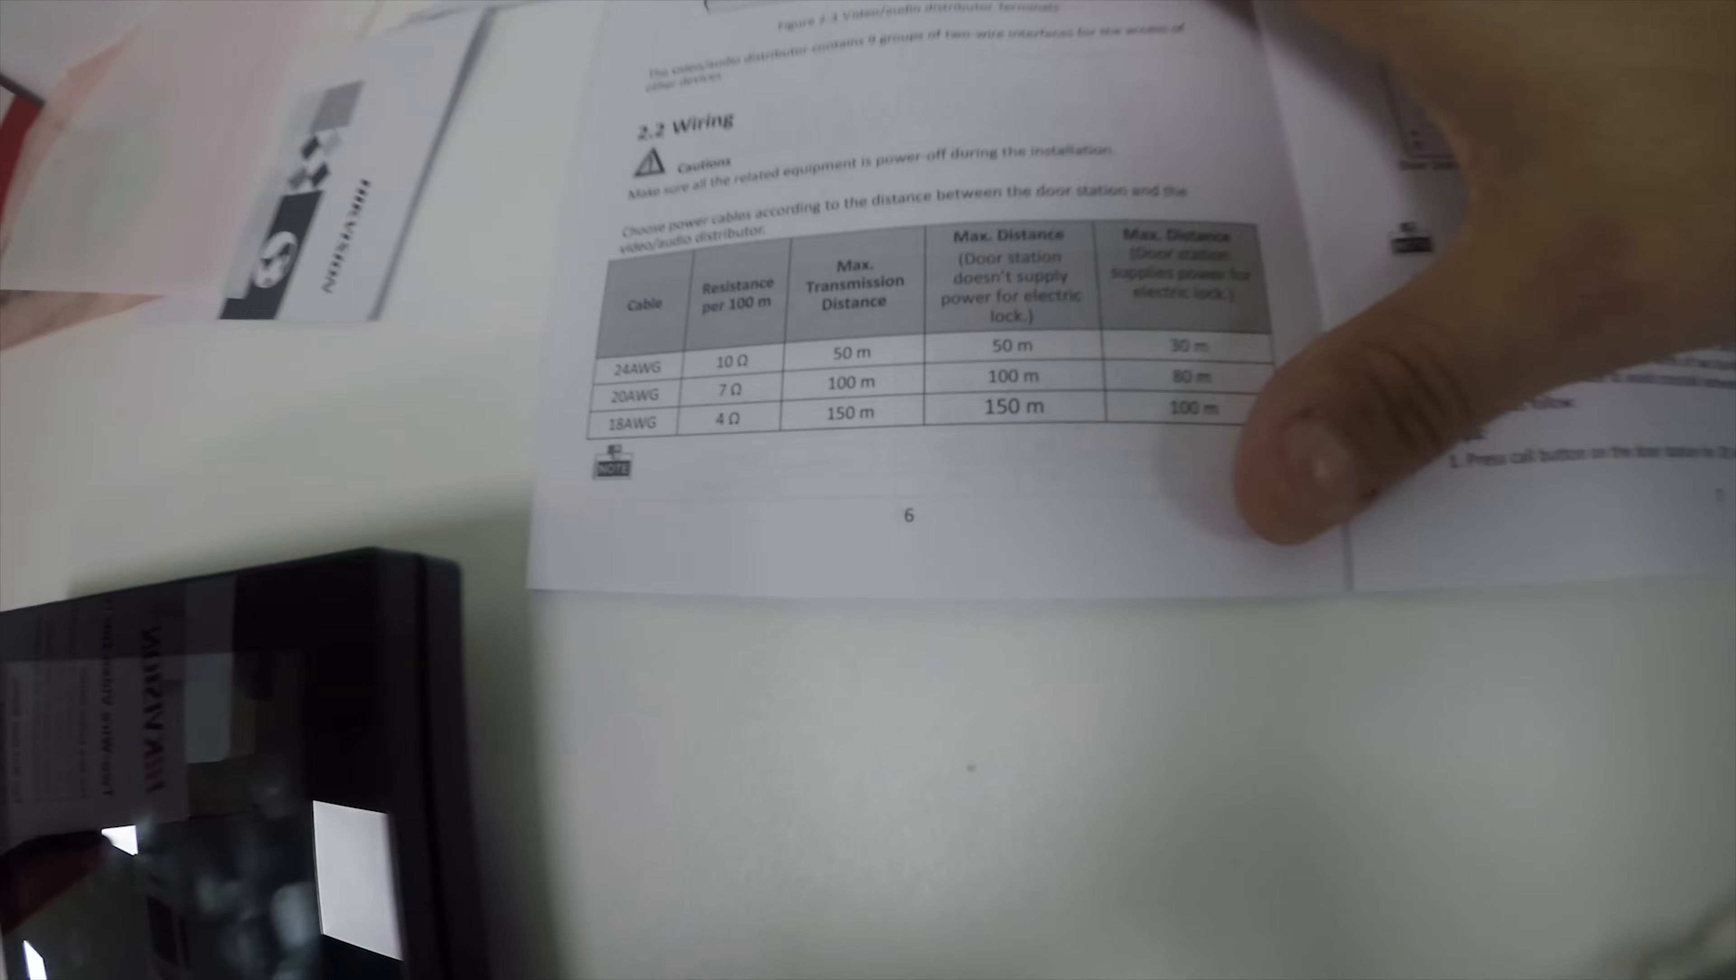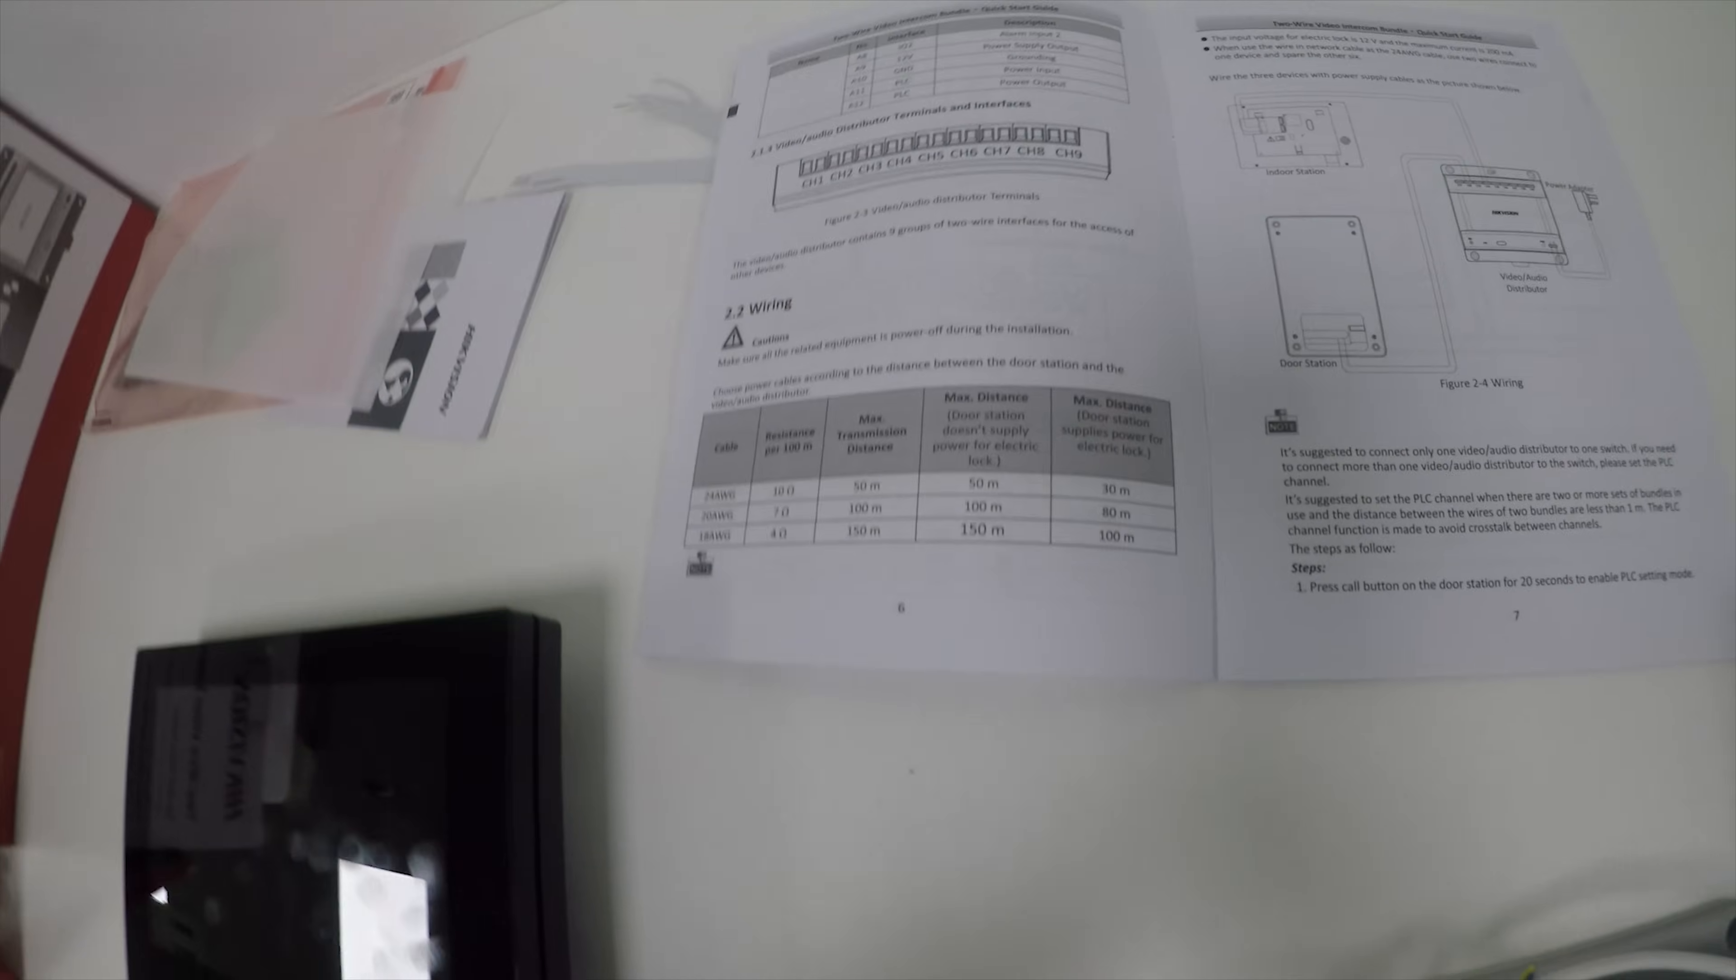We've got standard four-core alarm cable - about 25 meters between the power supply and door, and about 40 meters to the indoor station. The manual is really helpful with lots of connection details and tells you the distances. Depending on the cable AWG, we can support up to 150 meters without a lock supply or up to 100 meters if we power the lock from the distributor.